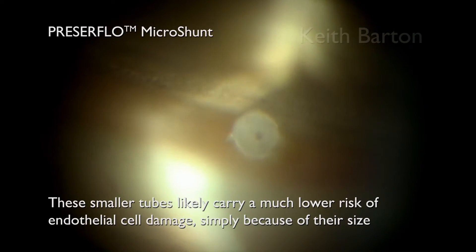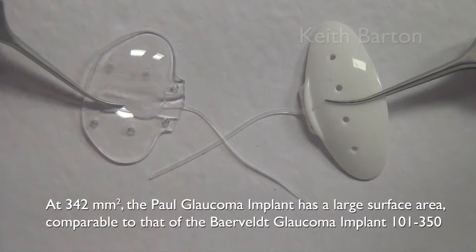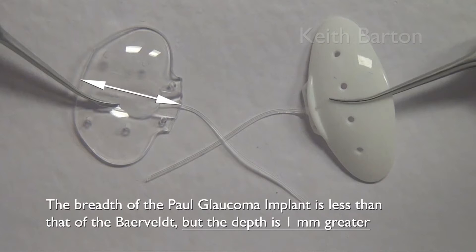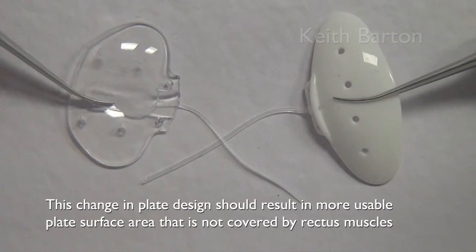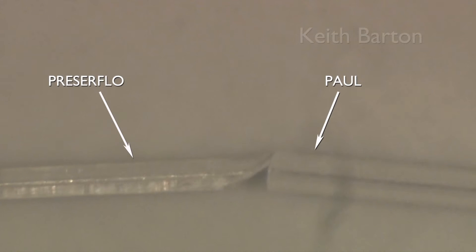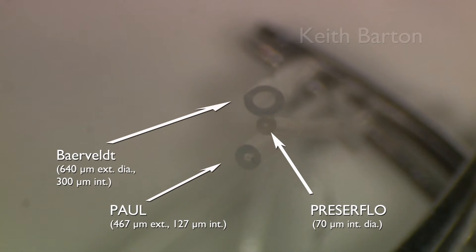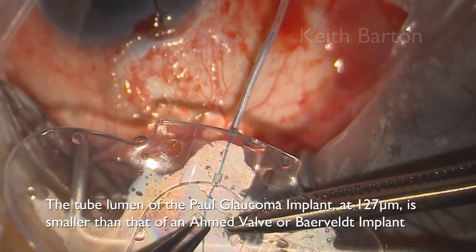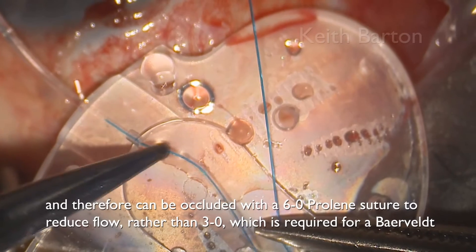These smaller tubes can likely carry much lower risk of endothelial cell damage simply because of their size. At 342 square millimeters, the Paul Glaucoma Implant has a large surface area comparable to that of the Baerveldt, but there are subtle differences — the breadth is slightly less and the depth slightly greater, which in theory should result in more usable plate surface area not covered by rectus muscles. The tube portion of the Paul Glaucoma Implant is much smaller than the Baerveldt and only slightly larger than a Preserflo. The tube lumen of the Paul Glaucoma Implant at 127 microns is smaller than that of an Ahmed valve or Baerveldt implant, and can therefore be occluded with a 6-0 Prolene suture to reduce flow rather than the 3-0 required for the Baerveldt.